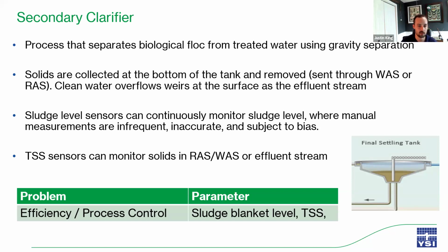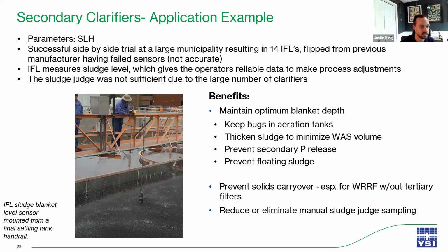So in this stage, having a sludge blanket level sensor can be really useful. Monitoring the sludge level height, or even monitoring TSS, can be used to help control the waste activated and the return activated sludge, which Adrienne talked a little bit about previously in this presentation. Sludge level sensors can be difficult to connect in certain systems or in plants in general, which I'll talk about in a couple of slides, because typically we find that secondary clarifiers are farther away from the rest of the plant and where we typically see instrumentation. In a couple of slides, I'll explain how IQ SensorNet can help mitigate the issue with running process instrumentation in more remote parts of the plant. But I would like to talk about this application example first.